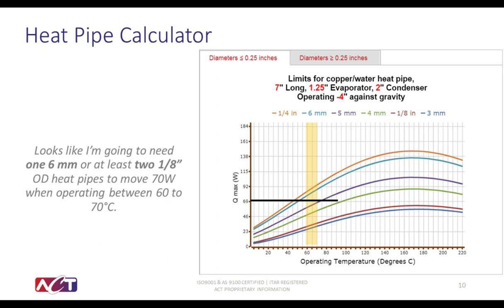The operating point is the 70 watts, which is shown on the y-axis of the chart, and the black line indicates that point. Knowing that we have to operate the heat pipe somewhere between 60 and 70 degrees C, we can draw that yellow bar across the chart.